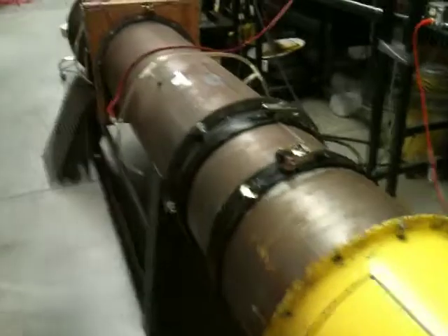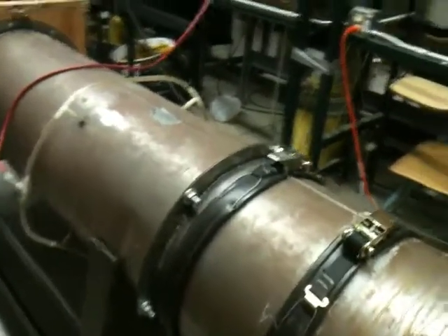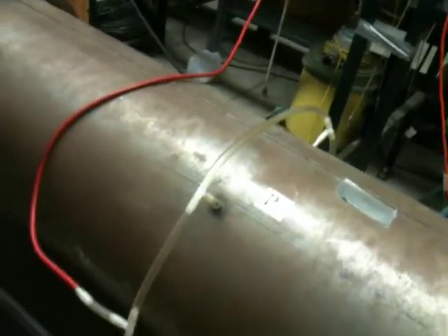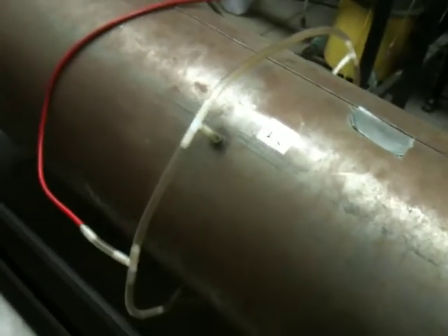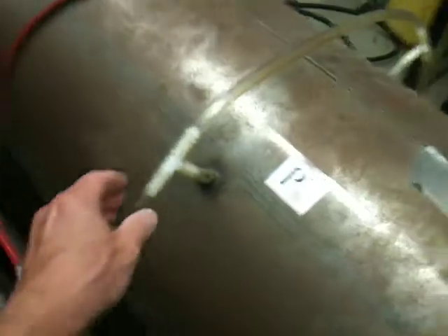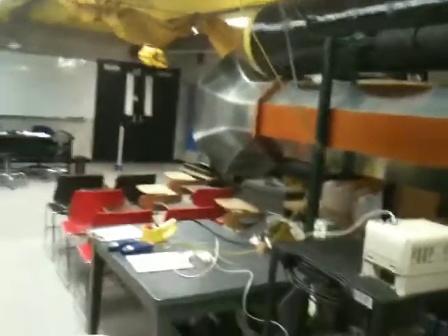Okay, we're almost done with the second segment for the fan test stand. I just want to show you the pressure taps and the duct in a little closer detail. Here are, again, the pressure taps for the P sub S, the fan pressure, and we've got 4 little tubes equally spaced, welded to the duct. They are connected to one another by T's, so they are giving us an average of all 4 pressure readings. And the tubing runs up and across that bridge there over to the table where that manometer is.